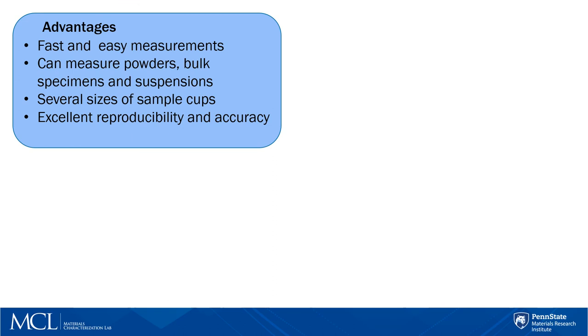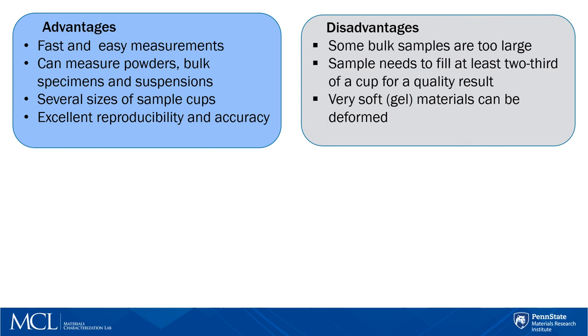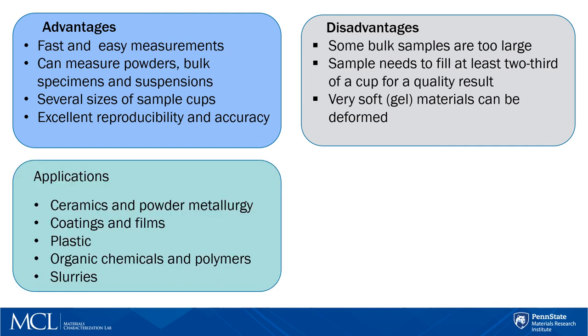To summarize, helium pycnometry provides easy and fast measurements. We can measure samples in different states and sizes, and this method gives excellent reproducibility and accuracy. However, there are a few disadvantages. Some bulk specimens can be too large to fit into the sample cup. Samples need to fill at least two-thirds of the cup for quality results, and this could be a problem if you have very little sample. Also, very soft gel-like materials can be deformed by the introduced helium pressure. Applications include ceramics and powder metallurgy, coatings and films, plastics, organic chemicals and polymers, and slurries.